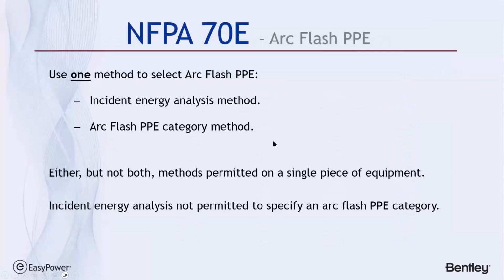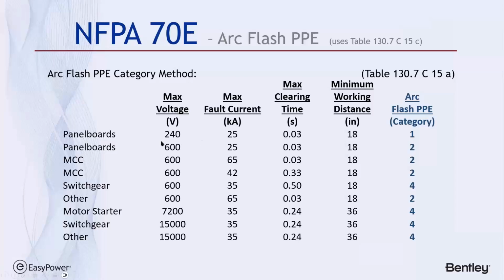Likewise, for PPE, we can also use the same table to determine what PPE is required. And again, NFPA 70E gives us a list of the equipment, the max current, the clearing time, the working distance, and then the PPE category. Again, I can't use this if I've done incident energy calculations, the incident energy method. So you might say, where or when do I use this? Primarily, it's available for people that haven't done an arc flash study and for some reason are having to do data collection on equipment that can't be turned off, in which case you can assume a worst-case arc flash PPE based on the definition of this table.